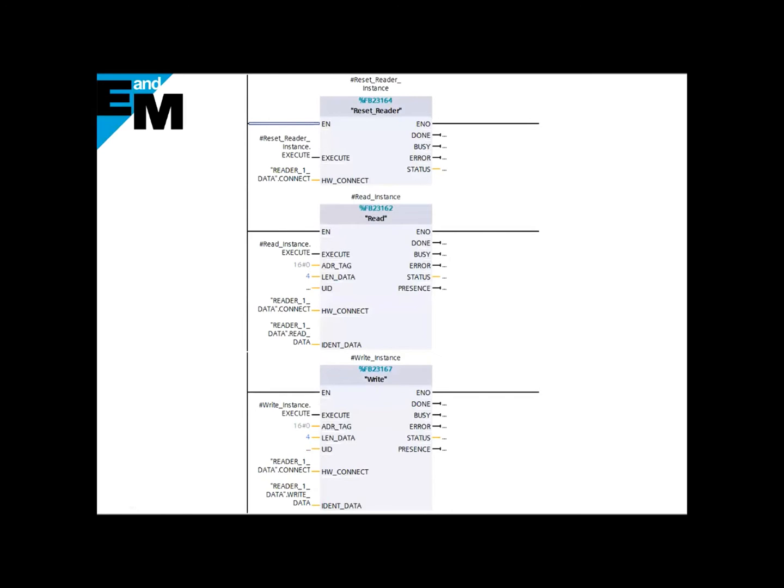Also, you can see on the right side there are way more options available, but they are all with three dots, which means they are not mandatory to be defined to compile the blocks correctly and execute the blocks. We can leave that without assigning any parameters to those blocks. Also, if you notice, there are error codes on each of the blocks, so each block can give us specific errors for diagnostics.